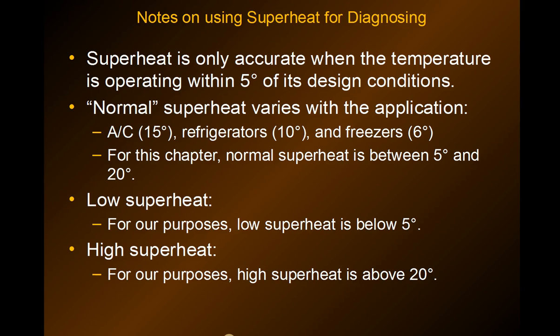Normal superheat for this chapter varies depending on whether it's an air conditioner, refrigerator, or freezer — that's on the cheat sheet you can download. But for this chapter, normal superheat is between 5 and 20 degrees Fahrenheit. Low superheat is below 5 degrees Fahrenheit, and high superheat is above 20 degrees.